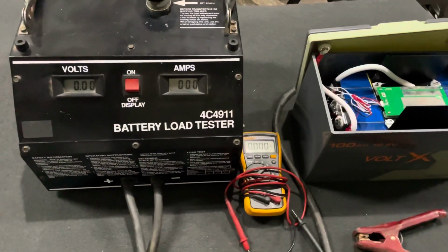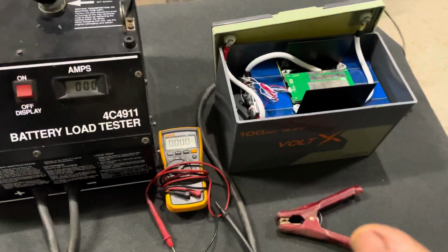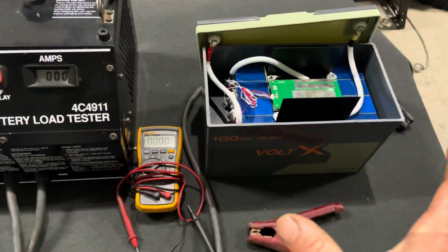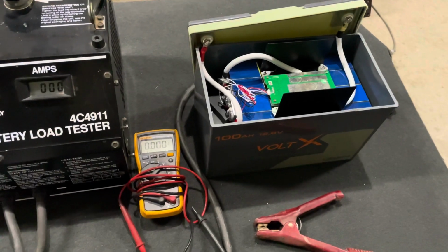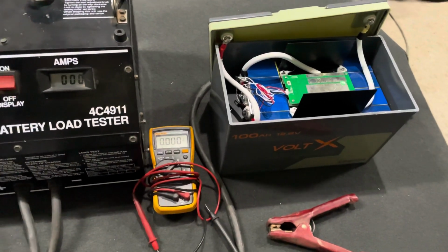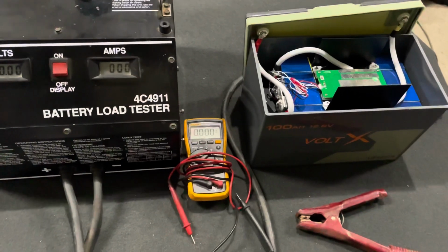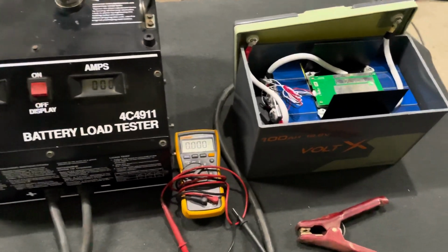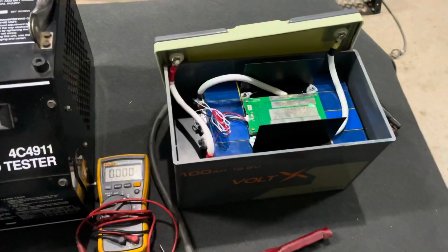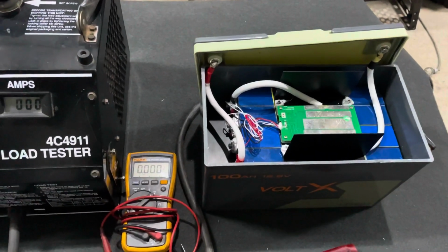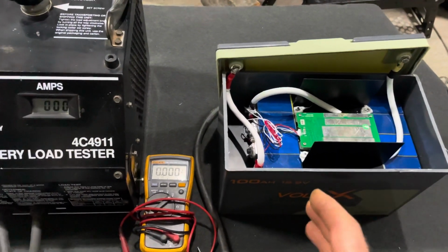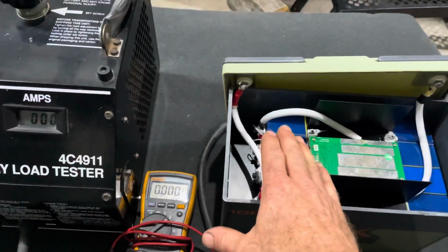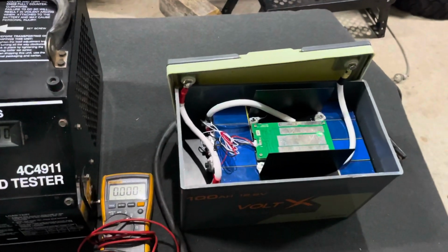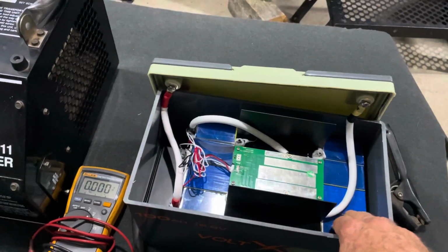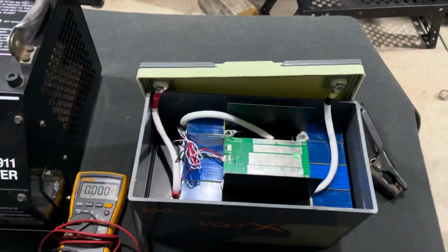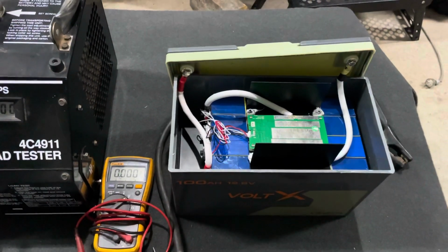I'm going to do a part 2 now where I parallel two of these batteries together, and I'll show you how to do that. We'll see if it actually will parallel up, because according to the VoltX website, you can't. From what I understand, there should be no reason why you can't if it's done properly. Then we'll install a cell balance port so I can externally balance each individual cell, because these cells discharge so differently from each other that I think cell imbalance is going to be an issue with this battery.